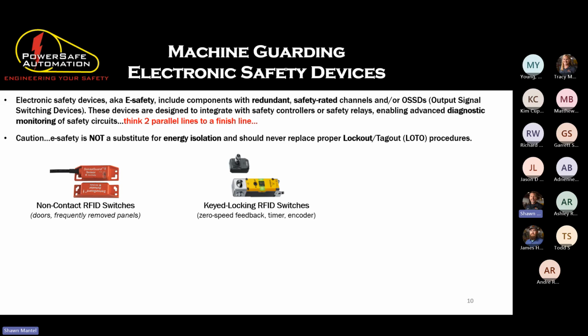When I open my door, my machine will stop. The switch will tell your machine to stop, but if it doesn't have an immediate brake and it has to coast down and it takes 10 seconds to coast down, you are now at that hazard for the next 10 seconds and could still get hurt even though you told the machine to stop. This is where you need to use keyed locking switches so that you have some sort of feedback that says I'm at zero speed, or a timer that says it takes 10 seconds to stop, so that when this machine stops, it will unlock the door and let you in.